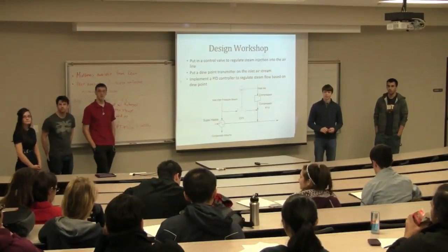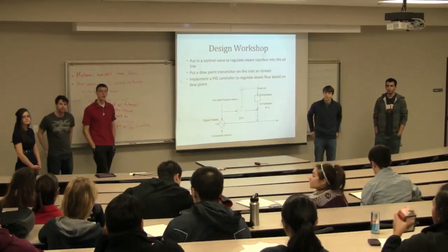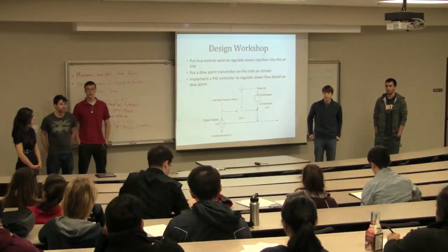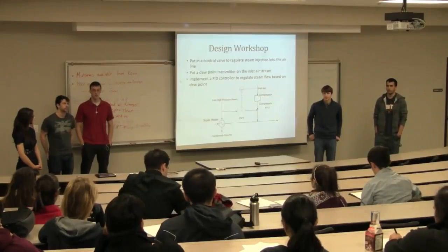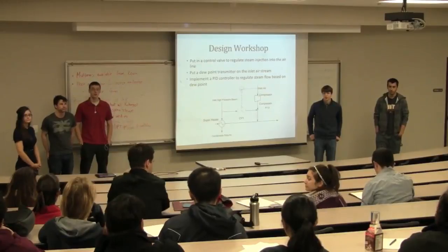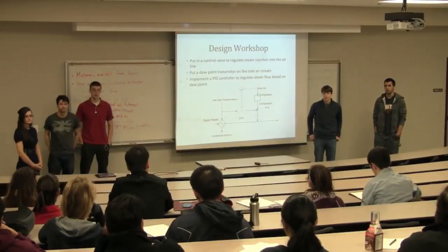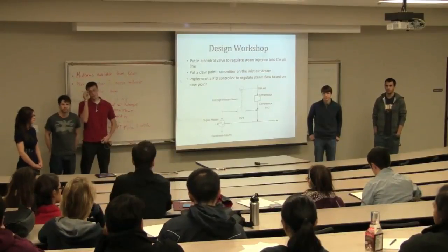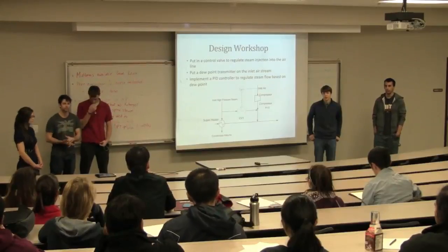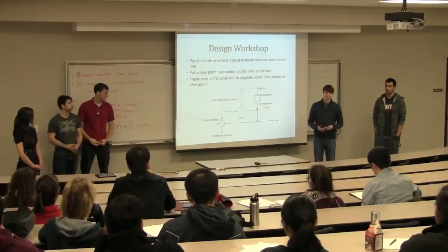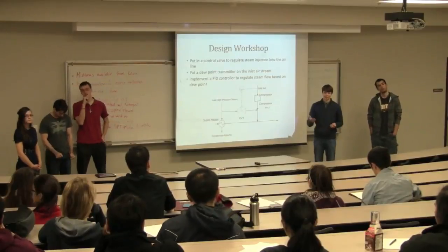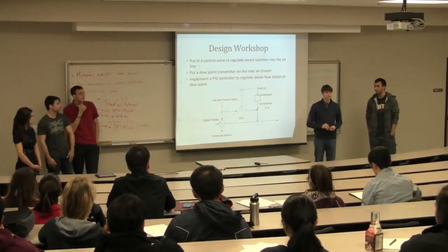Yeah, this setup here is pretty classical, that you've got drawn with the DPT sensors and inputs into, it's essentially just a disturbance rejection model in a feed-forward control loop. So you're implementing that portion of the loop. And so these calculated values based on inputs go to a calculation engine that makes a prediction on how much to open that steam valve. And then you assume that your model, that's essentially like a model predictive controller, is accurate. Yeah, it's a pretty robust model. It's a very understood and well-modeled system. It's low error in the model. Yeah, exactly. It's not very complex. Any other questions?